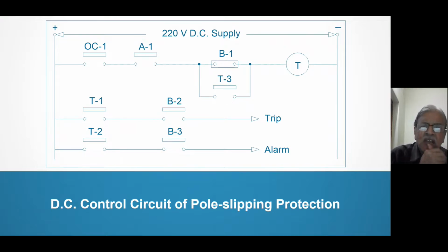circuit. And the relay is very costly also. We had purchased the relay for a very good amount, beyond 50 lakhs or something. The relay is costly because it has to be very sensitive, right? And it has to measure very small time, because the timer is set for hardly 5 or 6 milliseconds. So it is not like 10 seconds or 60 seconds or something. So the timer is very important, and characteristics A and B are also very important.